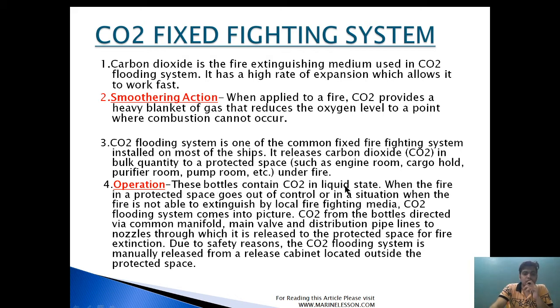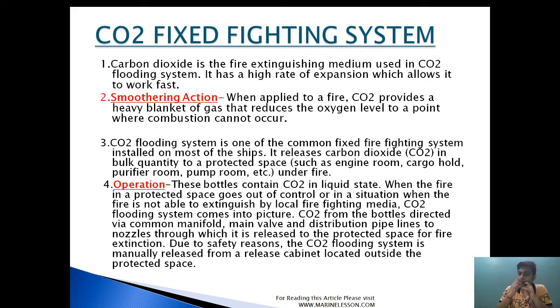The bottle contains CO2 in liquid state. When fire in the protected space goes out of control, or cannot be extinguished by local firefighting media, the CO2 flooding system comes into picture. CO2 from the bottle is directed by a common manifold, main valve, and distribution pipe to a nozzle, through which it is released to the protected space for fire extinction. For safety reasons, the CO2 flooding system is manually released from a release cabinet located outside the protected space.